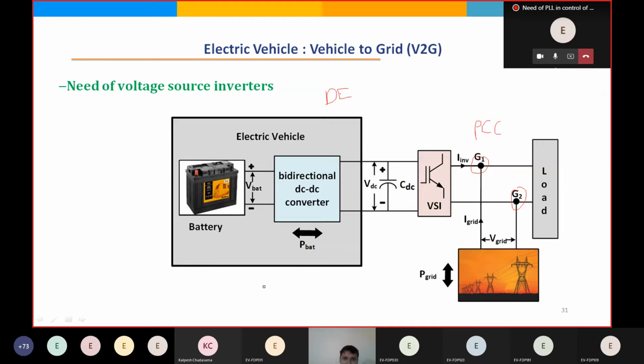And this can never be the master. The master is always going to be your grid. So the grid decides the frequency, the grid decides the voltage level. So the inverter frequency at the output of the inverter should match the grid frequency. The phase of the inverter voltages should match the grid voltages. At the same time, the voltage levels should match.